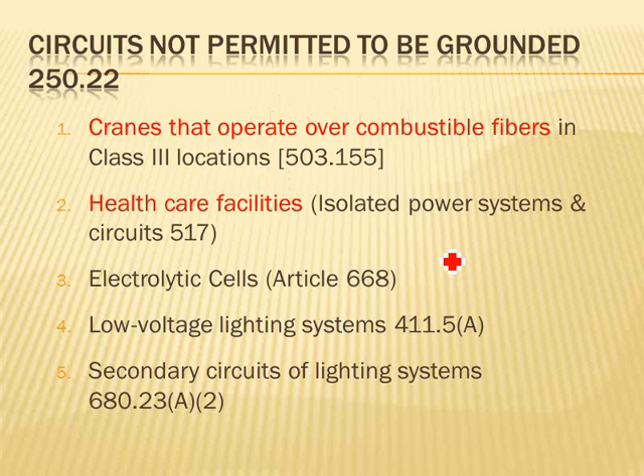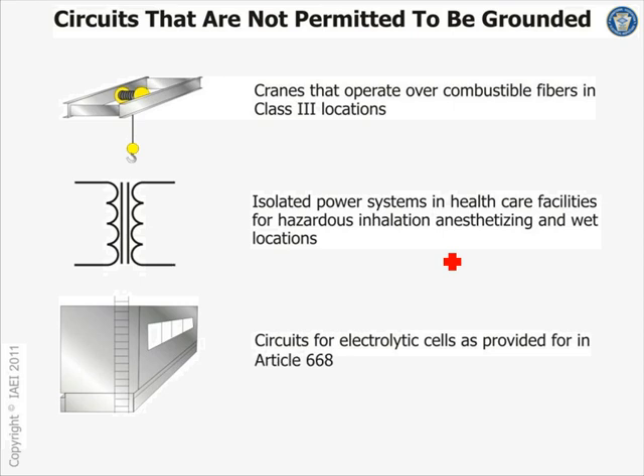Okay, circuits not permitted to be grounded. These are shall not, will not, even if you want to ground it. Number one, cranes that work over combustible fibers. If you have a crane working here, you cannot ground the power system that drives this crane. Anybody knows why? If a ground fault will arc over a crane, what do you get? Fire. So that's a fire hazard.